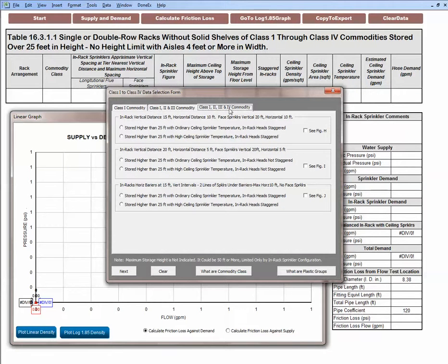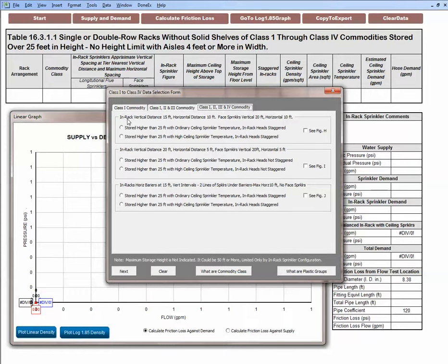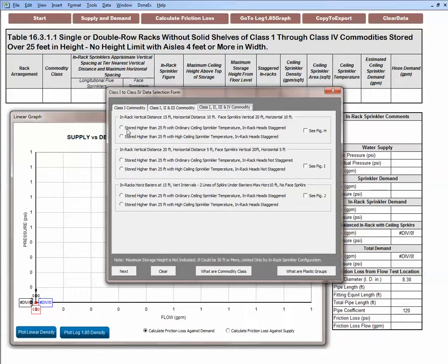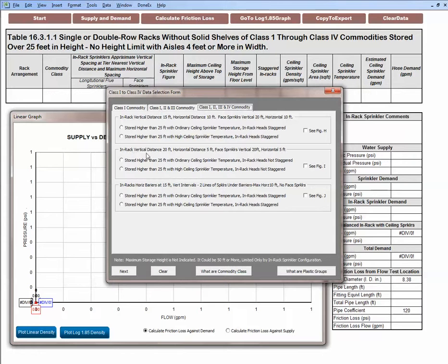I'm looking for class 4 commodity and there are three areas to enter data. The data that I enter is based upon the in-racks. I have two levels of in-rack sprinklers and two levels of face sprinklers and the levels are 20 feet apart. So we're looking at this area: in-rack vertical distance 20 feet apart.